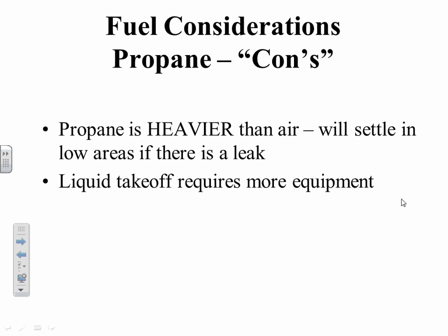So they still have this equipment sitting up on top of high hills. And they had one where they actually had a generator set inside the building, and it was propane. There was a leak, and this was back in the days when they had relays instead of solid state stuff. And it took that repeater site off the top of the mountain with an explosion. So, nasty situation. It is heavier than air, and I've told consultants for a lot of years now, don't put them inside. These are outside units only.